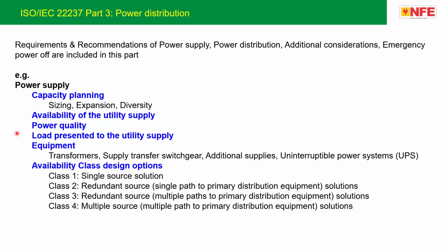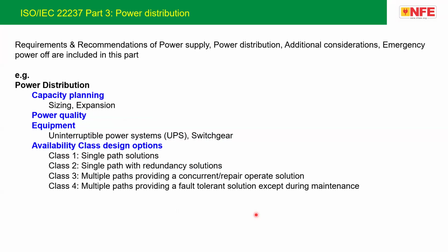Class 3 is multiple paths to the primary distribution equipment with a redundant source. In this class 3, a fault of a functional element shall not result in loss of functional capability, and plant maintenance shall not require the load to be shut down. In class 4, multiple paths to the primary distribution equipment with multiple sources, a fault of a functional element shall not result in loss of functional capability, and plant maintenance shall not require the load to be shut down. So class 4 is the best one, but in that we require dual multiple paths and multiple sources. This is the way we have to design the power supply.